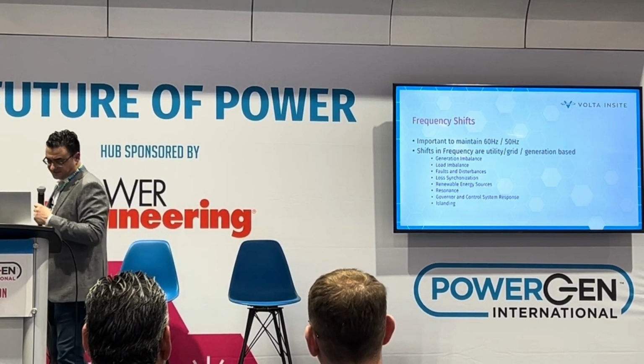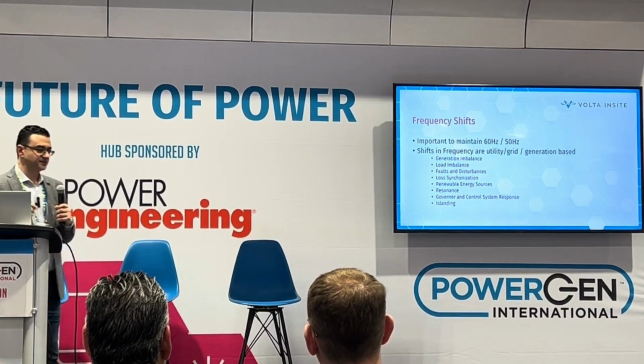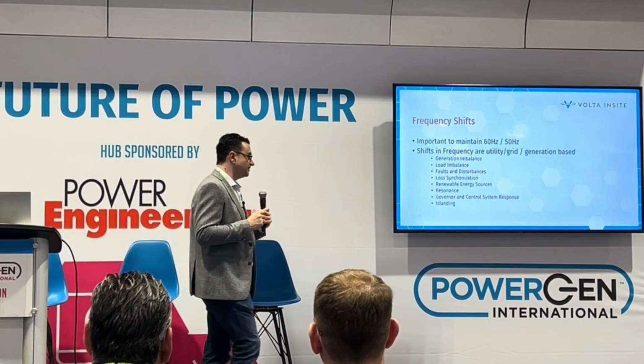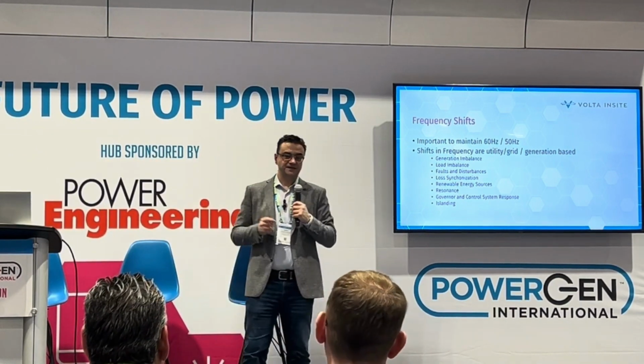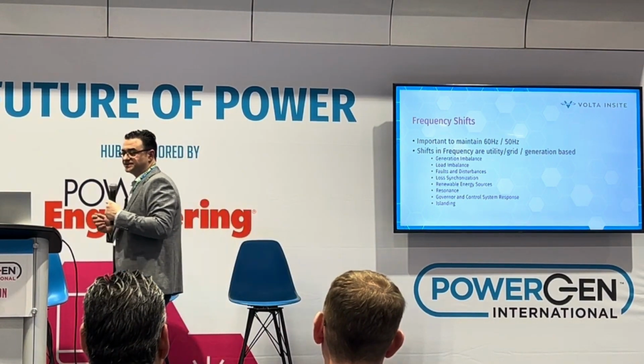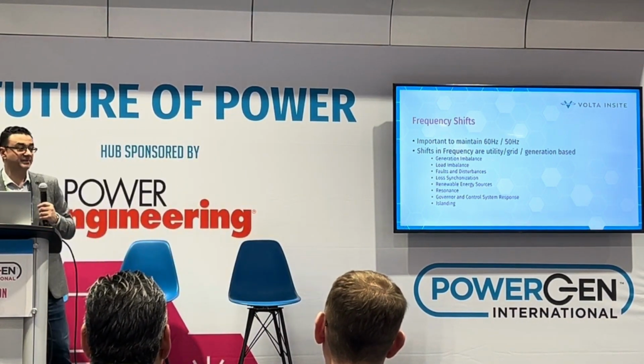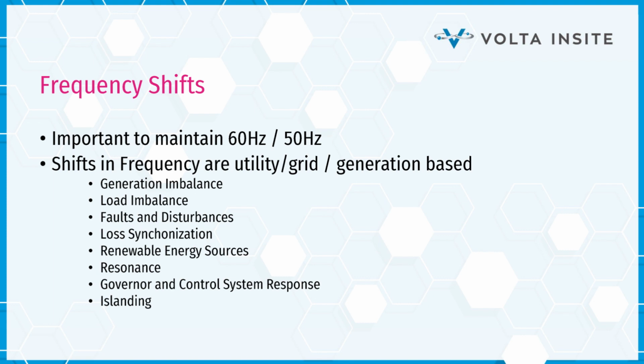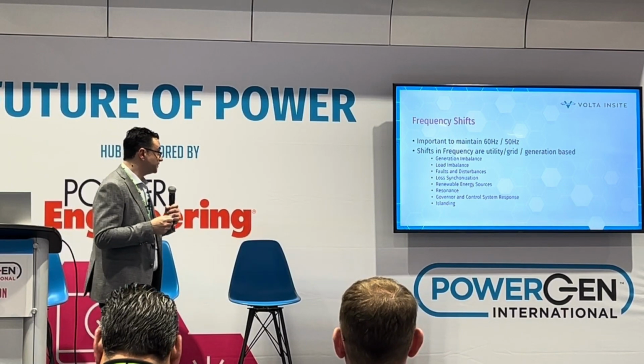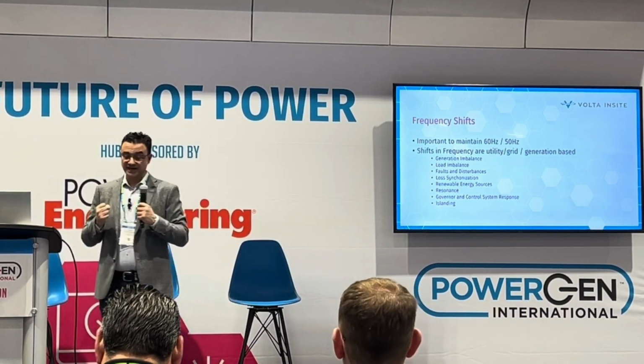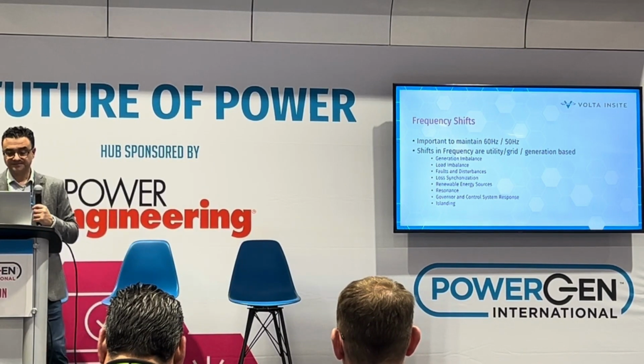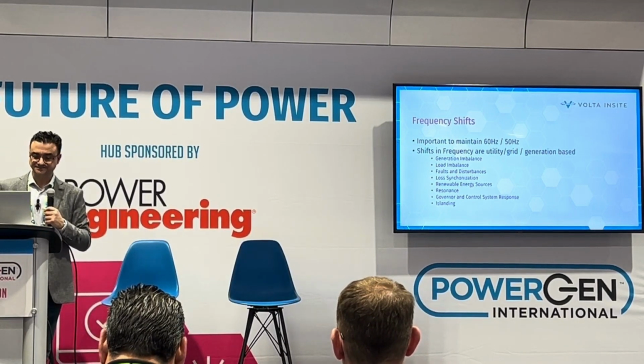Frequency shifts usually come directly from the utility, and there's not much you can do within a facility, so you can't affect frequency. Frequency shifts happen because of generation imbalance. If your utility is loading up one phase significantly, to the point of overload on the generation side, you will get a frequency shift. Load imbalance, faults and disturbances: anytime you have a short circuit condition within a utility, you will pull a large amount of current, and that will slow down the system.